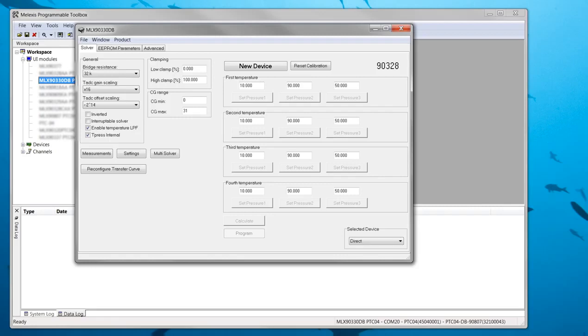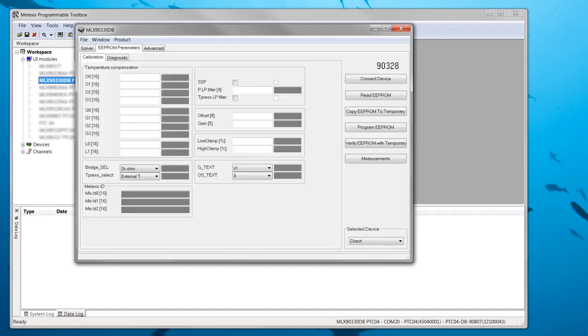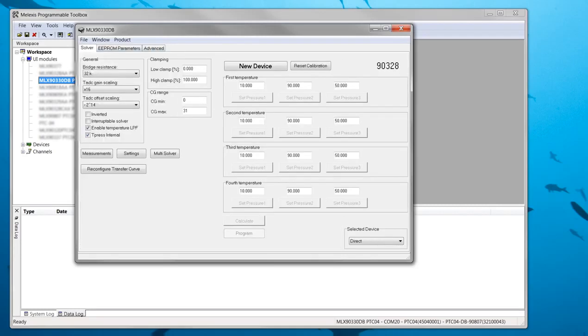When you first open the user interface, it will open in the Solver tab. This is one of the three main tabs which group together various functions. The Solver tab is used to calibrate a pressure sensor. If you're using factory calibrated products from Melexis, it is not needed to calibrate the device yourself. In that case, it is important not to press new device or reset calibration, as this can override parts of the factory calibration. A separate video explains how to use this tab to do a full calibration and how to easily modify an existing calibration.